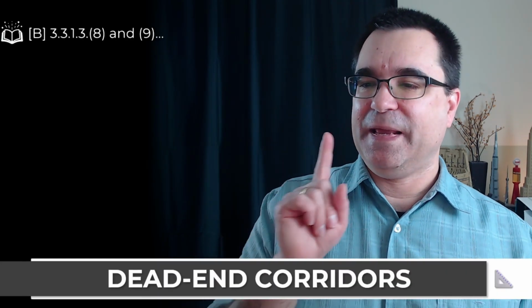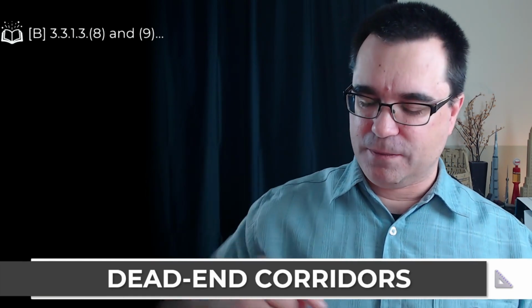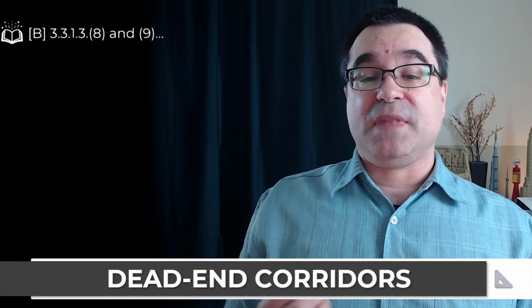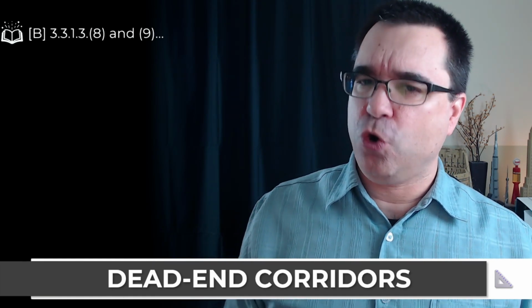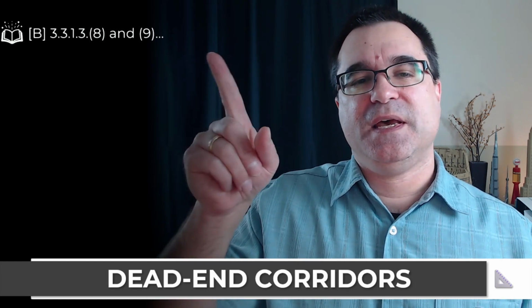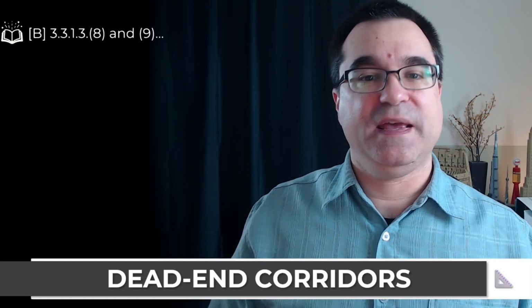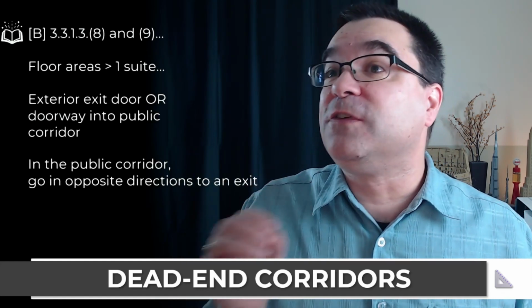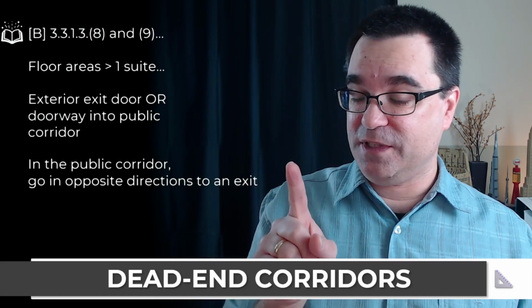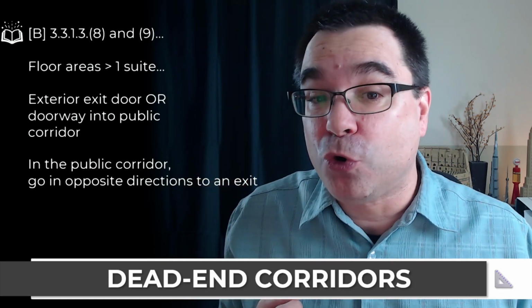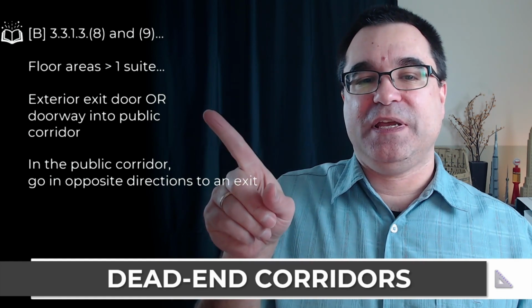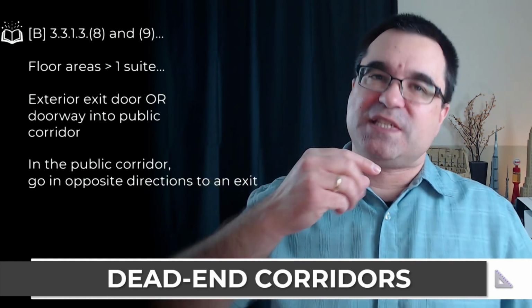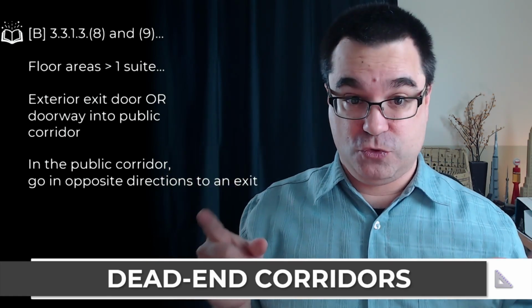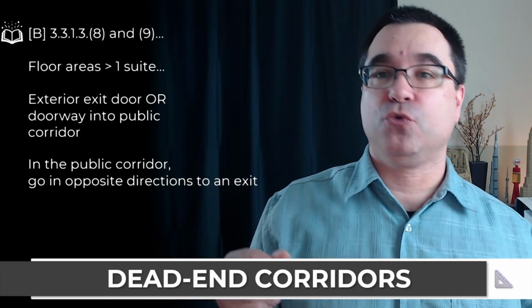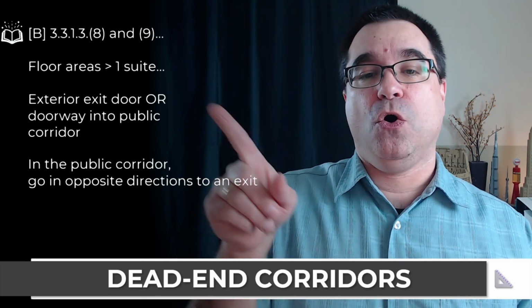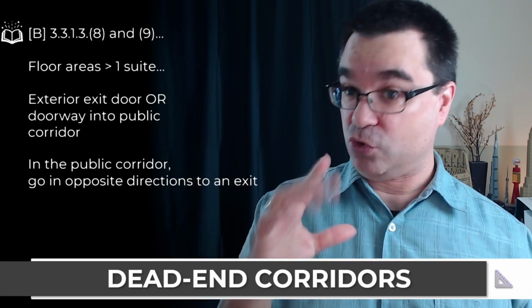All right. Now, I want to move on to this topic here because it's relevant and important, because it relates to so-called dead-end corridors. Under sentences 3.3.1.3 and 8 and 9, for those floor areas that have more than one suite, so basically the ones that have a public corridor, you should be able to exit any one of those suites either through an exit door in that suite or through a doorway into a public corridor, typically.